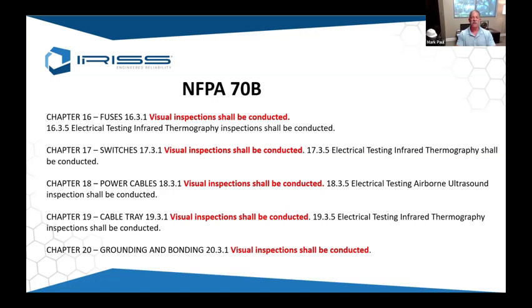Here's where this comes into play. The standards have changed. NFPA 70B 2023 changed from recommended to shall be. Shall be is the strongest form of you must do this, a legal way of saying this is not an option anymore. Going through the different parts of 70B, I highlighted a few chapters, and each one says visual inspections shall be conducted. At a minimum it's a yearly inspection based on the condition of the device, though sometimes it's required more than once a year.